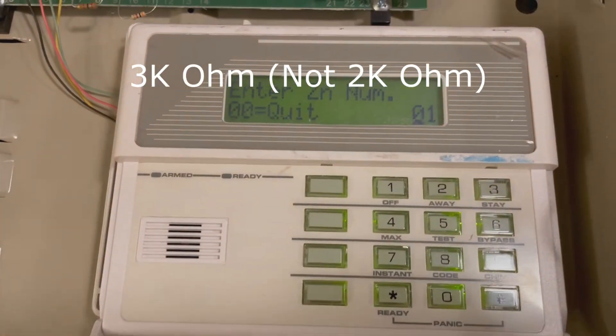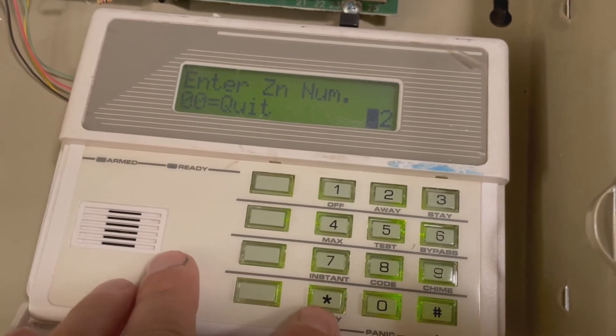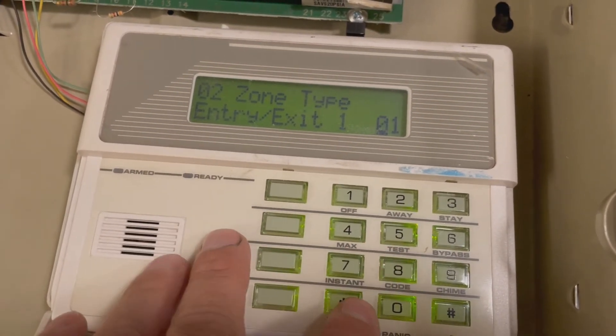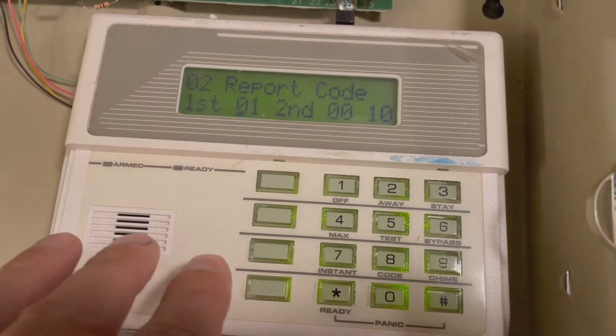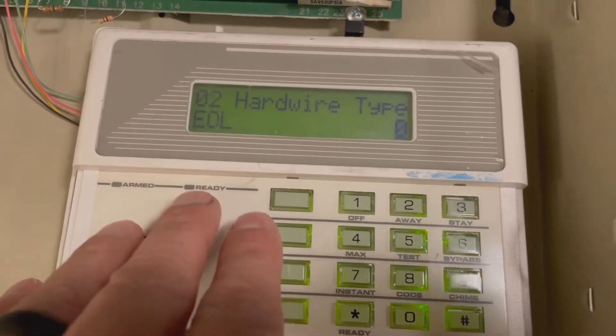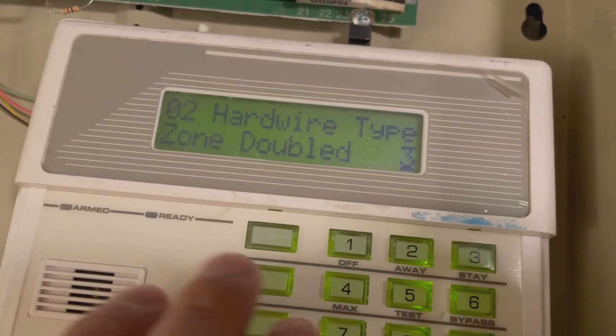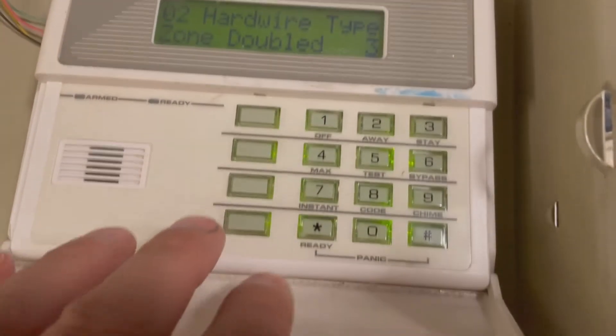To change zone 2 to a 3k ohm, I'm going to go to zone 2 — press 0, 2 for zone 2, then press star. This shows your current settings. Press star again. Don't change the zone type, leave that alone. Don't change the partition, press star again. It has the report code — leave that alone, press star again. Hardware type — this is what you need to change. It's currently 0. We need to change it to type 3, or whatever type your manual says for zone doubled. Once it says zone doubled, press the star key to confirm.